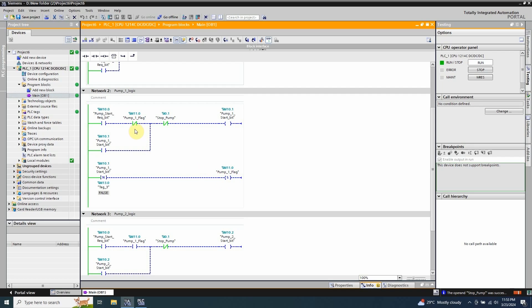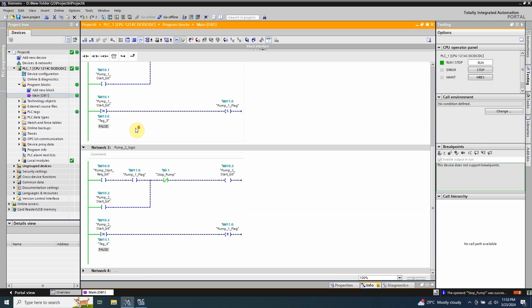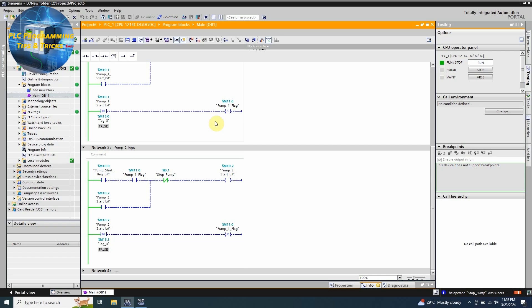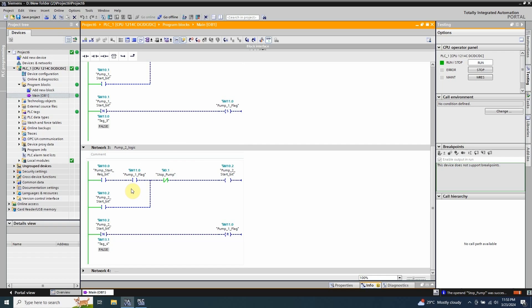This normal close contact M11.0 will be opened up, and this will prevent pump 1 from turning on next time. Now next time when the pump start request turns on, this pump 1 flag bit M11.0 is already closed. This will complete the logic path and latch on the pump 2 start bit, and pump 2 turns on.